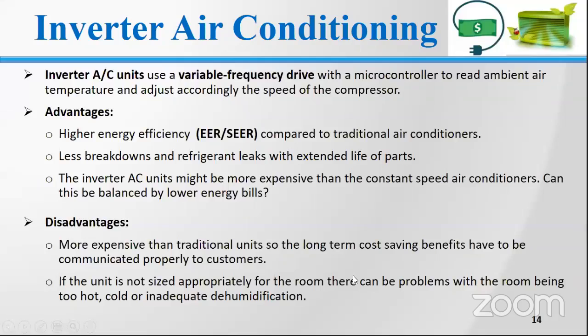There's also inverter air conditioning technology, which is becoming popular now in Trinidad and Tobago, and has definitely been around for a long time in the other Caribbean islands. These units are a little more expensive than traditional units, and they look exactly the same—the only difference is what's inside, which is a variable frequency drive, similar to what I mentioned before that they install on pool pumps. They have these drives built in that help adjust the speed of the compressor motor. This not only saves energy, but could also reduce the frequency of maintenance and repair problems and refrigerant leaks, and could extend the life of your air conditioning systems.